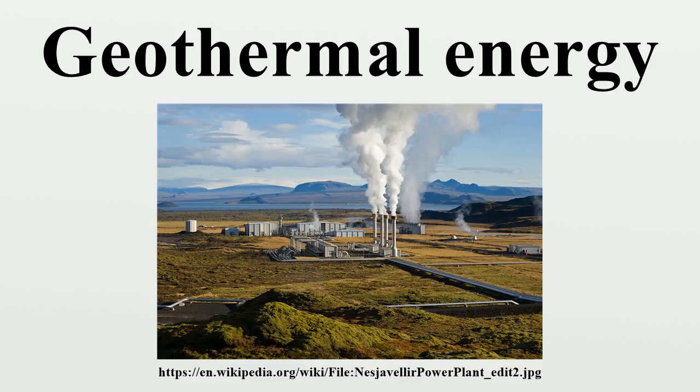Even though geothermal power is globally sustainable, extraction must still be monitored to avoid local depletion. Over the course of decades, individual wells draw down local temperatures and water levels until a new equilibrium is reached with natural flows. The three oldest sites, at Larderello, Wairakei, and the Geysers, have experienced reduced output because of local depletion. Heat and water, in uncertain proportions, were extracted faster than they were replenished. If production is reduced and water is re-injected, these wells could theoretically recover their full potential. Such mitigation strategies have already been implemented at some sites.